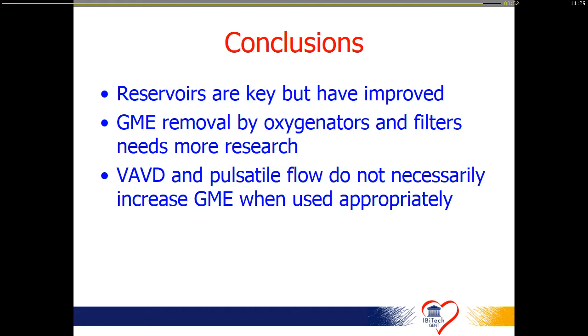For the oxygenator, I'm not always convinced that what we do now, an attachment of an arterial filter to the oxygenator, by itself solves the problem. The benefit of it is that it gives us the correct location, and it's a forced location, you cannot change it. So that's certainly a benefit. But I'm still not convinced that it should be at the end where you have the smallest bubbles. So you could really question if we would have it, for example, just before the fiber stack, and we remove it there, then the smaller ones will be captured inside this bundle and probably will be better removed than now, because after they pass the screen now, there is nothing which will remove them beside the tissue of the patient.